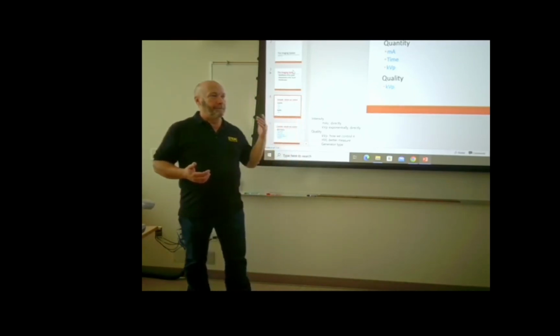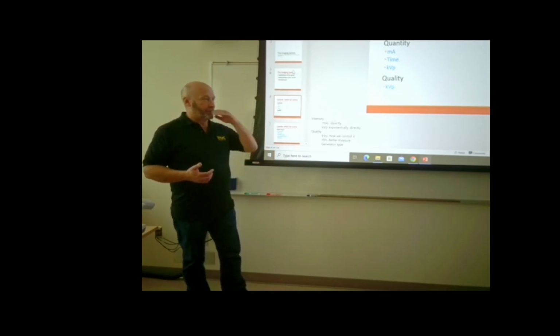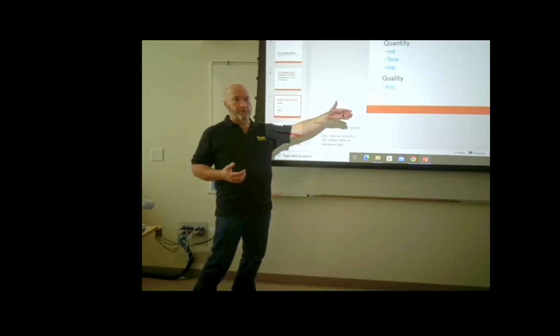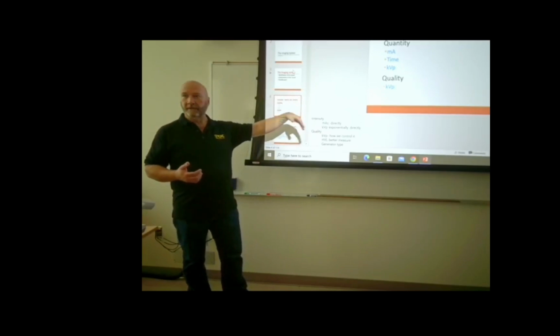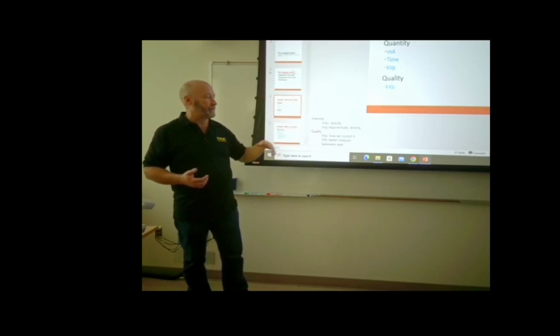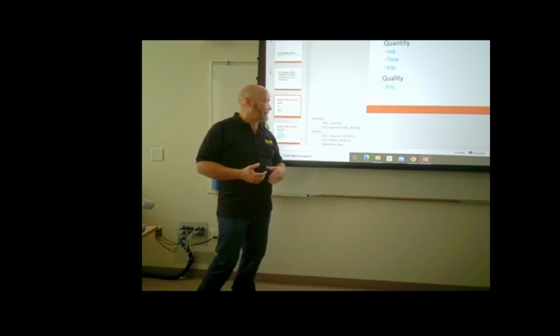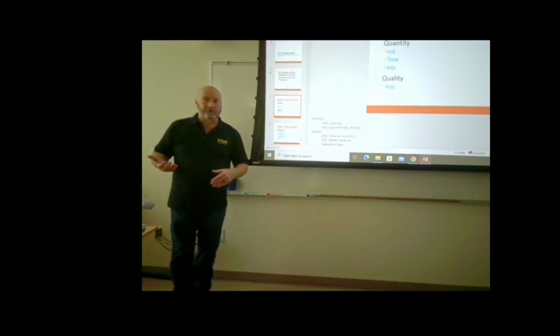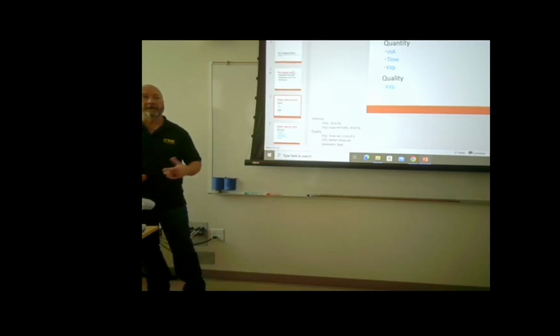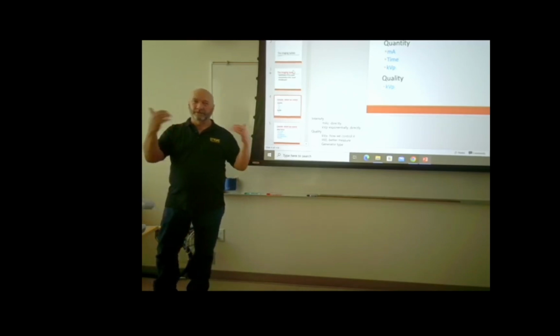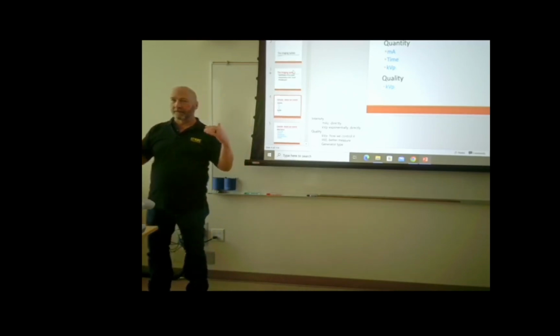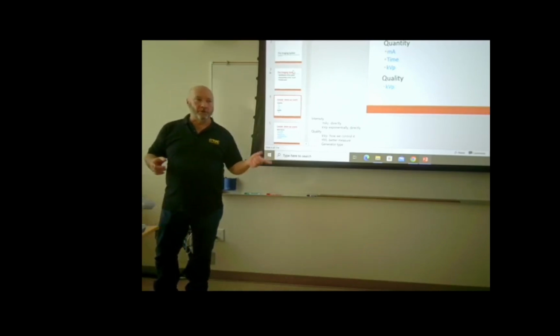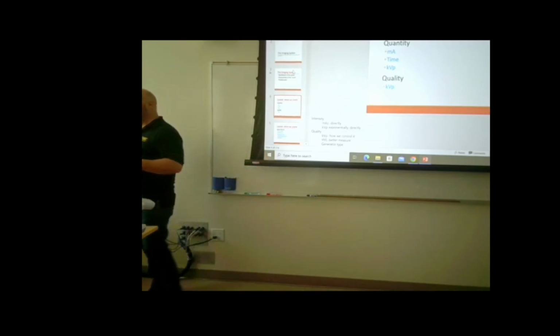The better measure of quality, kVp is a measure of quality. Quality is affected by kVp, it's affected by filtration as well, but the better measure of quality is your half value layer, right? And you kind of remember the little math thing that I ran through, comparing two different rooms, brand new room versus an older room. The older room would have more inherent filtration because of tanning of the X-ray tube.